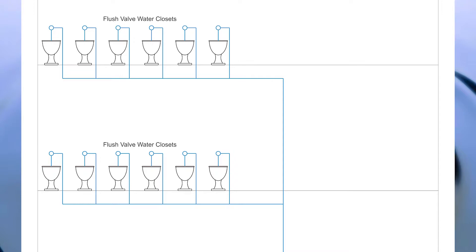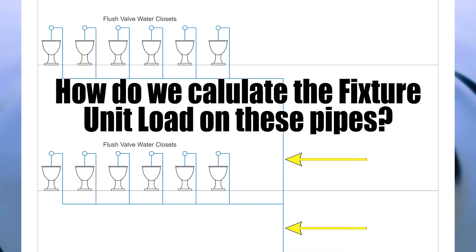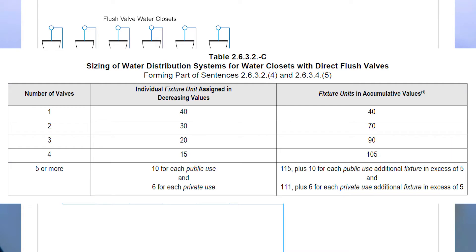Clarification number two: we have direct flush valves on multiple stories. How do we calculate the fixture unit load for these different pipes? In this example I have 12 flush valve water closets, six on each of two different stories. Now let's reference table 2632C to assign a fixture unit value for each of these water closets, and we're going to do both stories simultaneously because we've already done this before in a previous video.